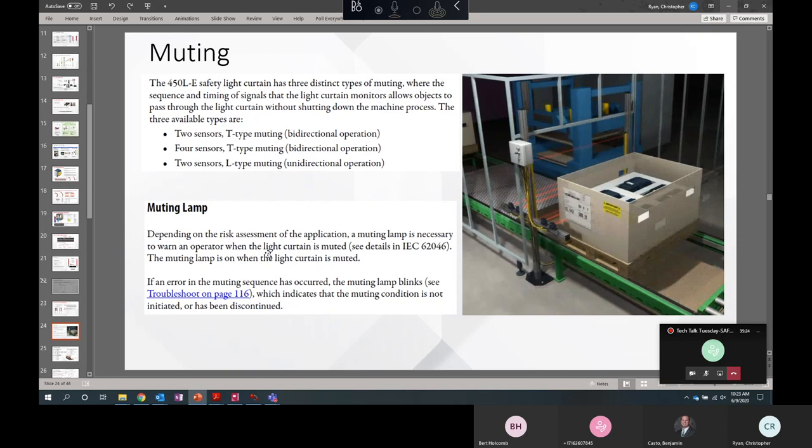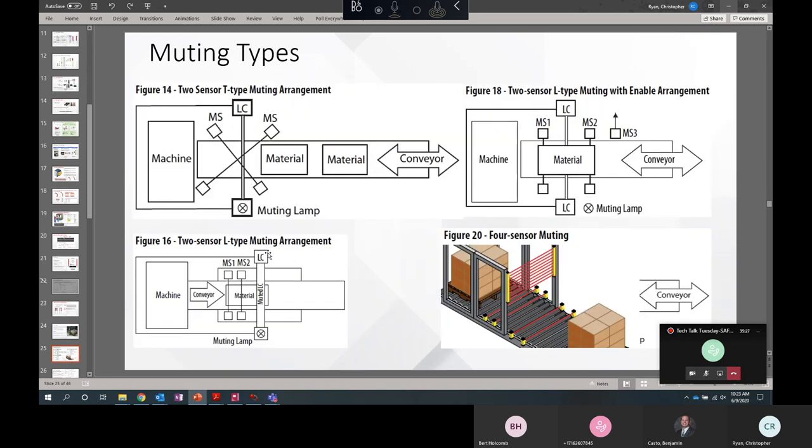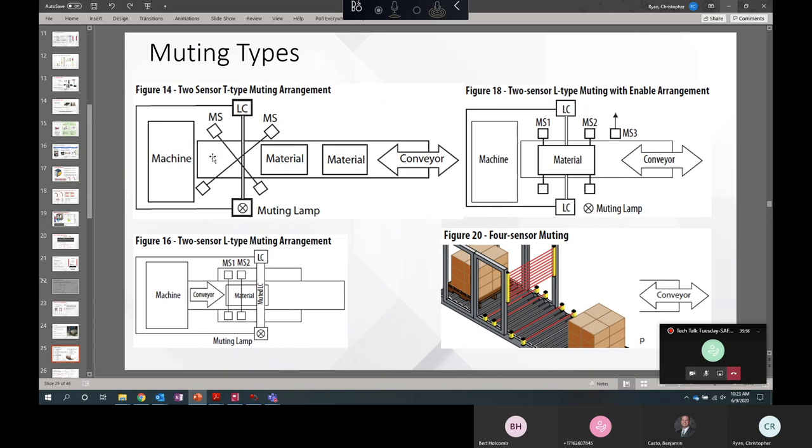So these are the different muting types. T-type and L-type refers to the shape of the light curtain and muting sensors when viewed from the side. The sensors will be arranged in the shape of an upside-down capital T if the muting sensors are on both sides of the light curtain. Or they'll be arranged in the shape of a capital L if muting sensors are only on one side of the light curtain. So on the top left, we've got the two-sensor T-type muting arrangement. I want you to notice that these muting sensors are arranged asymmetrically. That is so that the material passes the light beams at different times. So it'll pass this muting sensor, then this one, then the light curtain. It'll be muted. And then it'll unmute itself once the material passes this sensor.